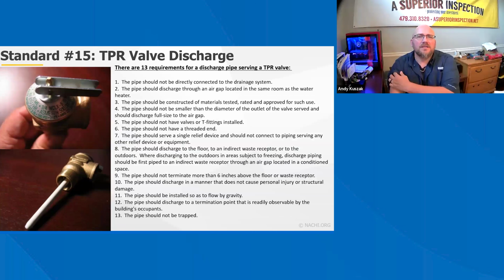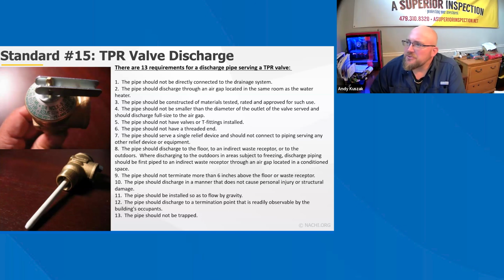All right. TPR valve discharges. An appliance used for heating water or storing hot water must be protected by a relief valve. A combination temperature and pressure relief valve, or separate temperature relief and pressure relief valves, prevent water heaters from exploding. They are emergency devices. They are not intended to continue to function continuously. The pressure relief valve should be set to open at least 25 psi above the system pressure, but not over 150 psi. The relief valve setting should not exceed the tank's rated working pressure.